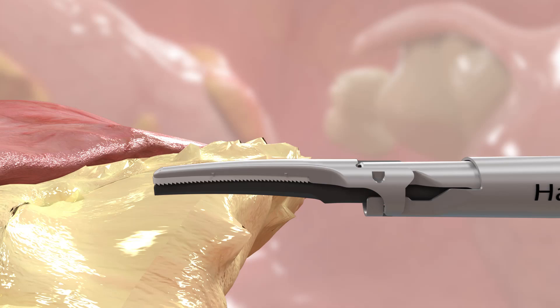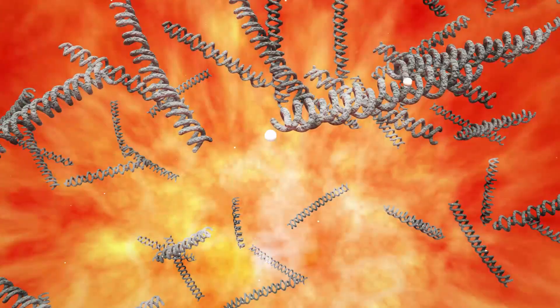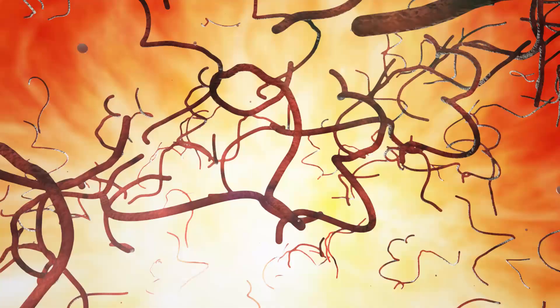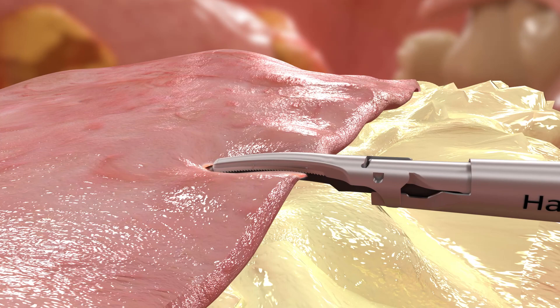This motion creates frictional heat when in contact with tissue, first coagulating then cutting tissue and vessels. No electricity ever passes through or to tissue or the body. Frictional heat breaks down hydrogen bonds, denaturing proteins and creating a sticky coagulum. Along with uniform compression and time on tissue, cell walls are coapted forming a strong seal, and then transection occurs within seconds with minimal lateral thermal spread or surgical smoke.